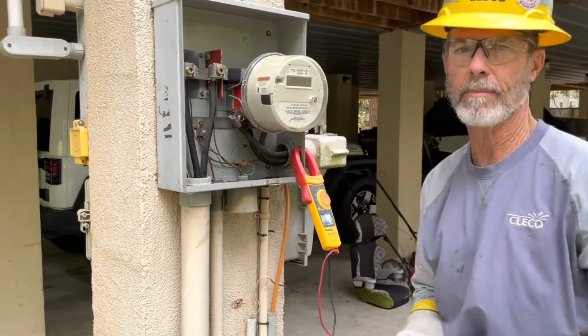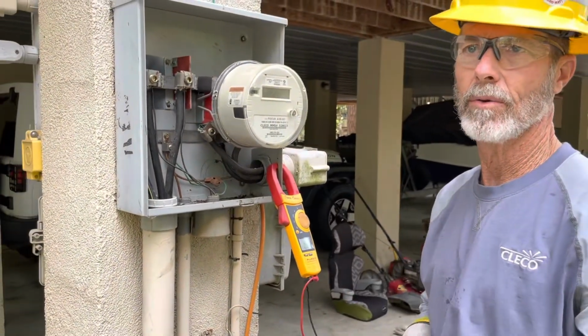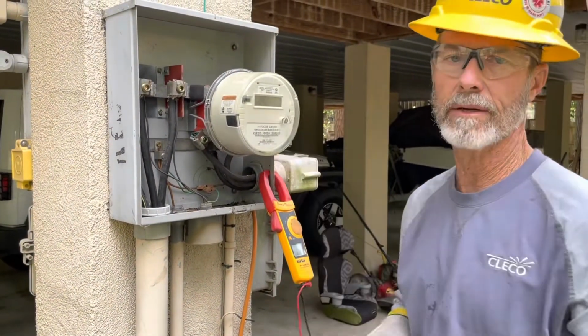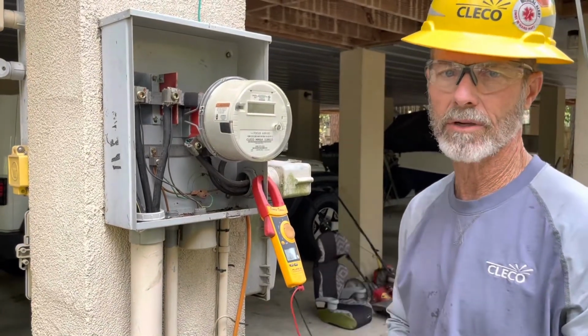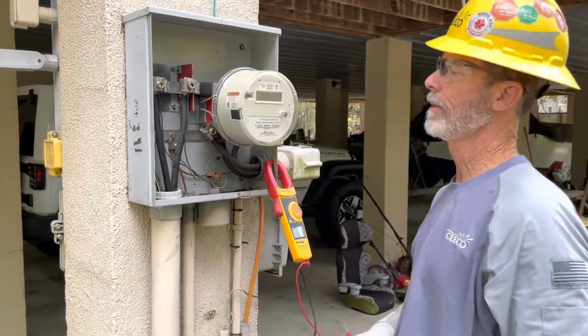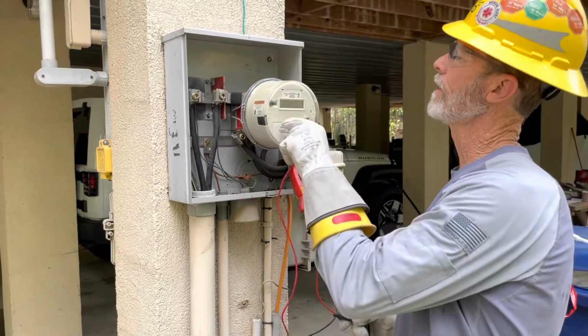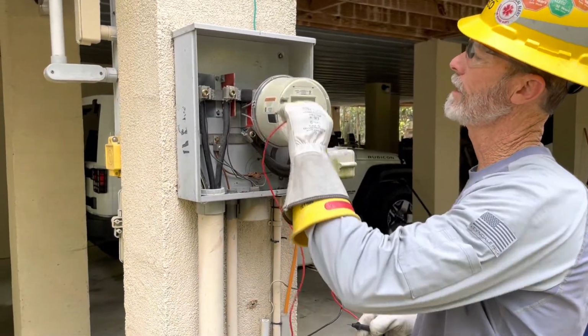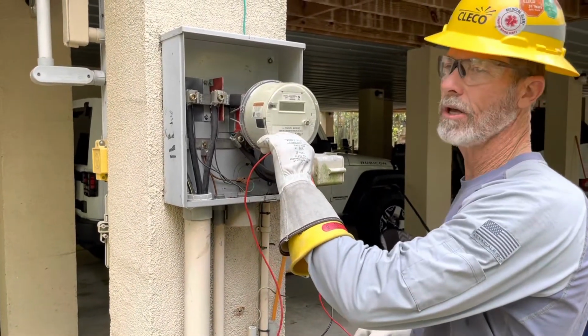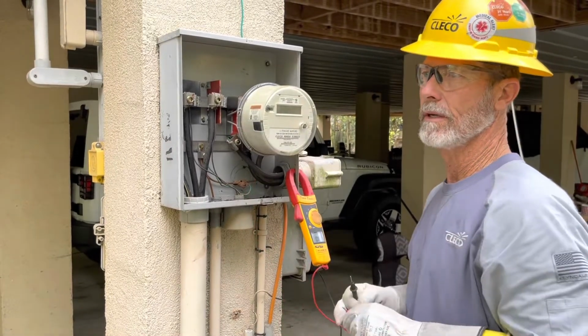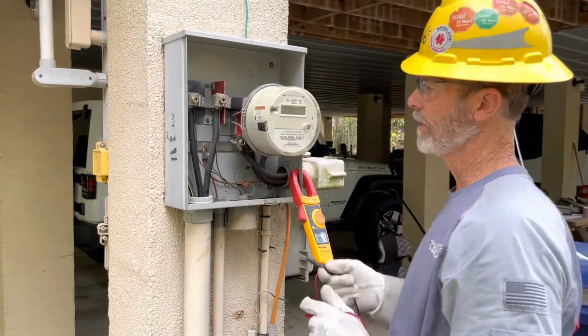Another check that we have to make with these meters is we have a disconnect built into these meters. And before we leave this service, we always should make this check to make sure that the little breaker that closes the line to the load is closed properly, because sometimes those breakers don't make a good contact.